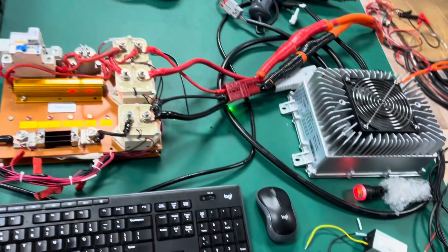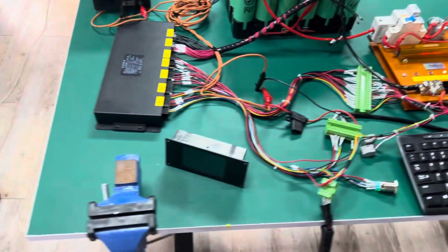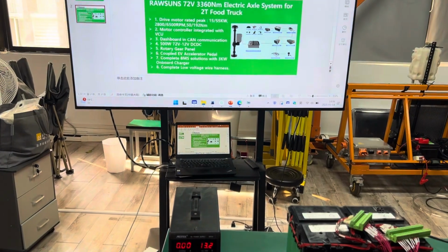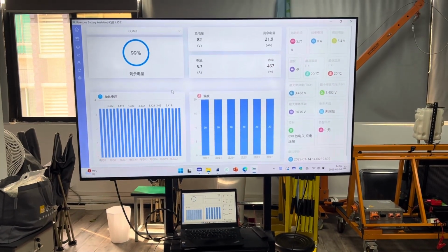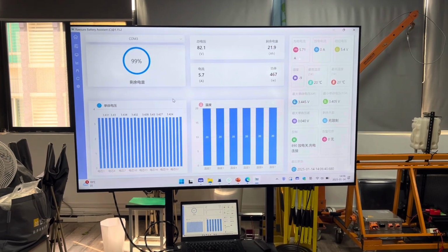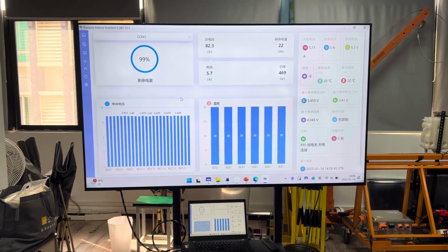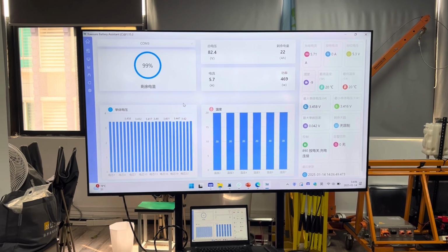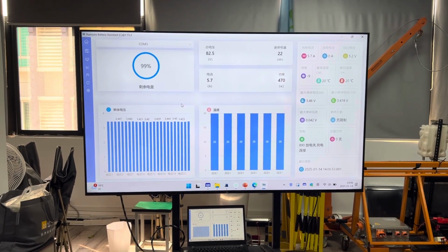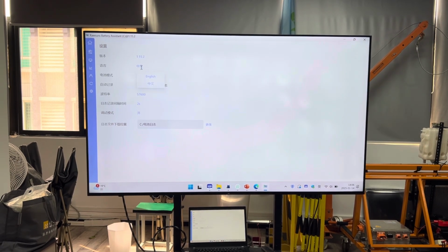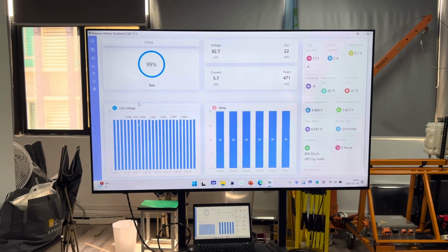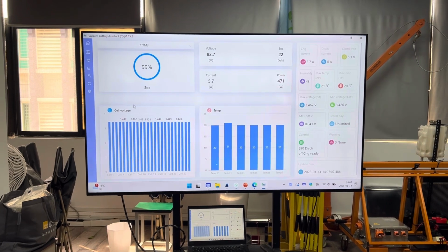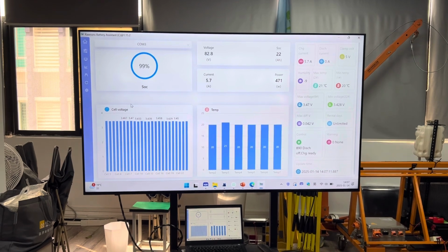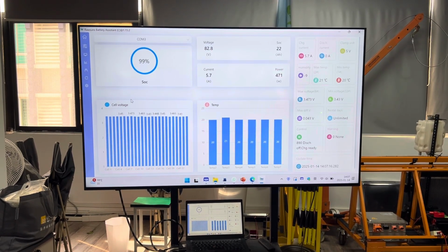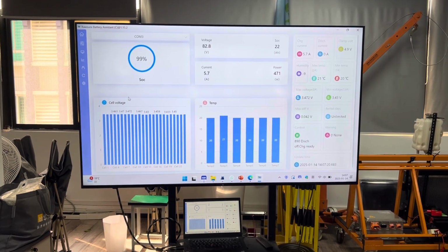now the 3 kilowatt charger is connected to the BMS system. We can have a look at our software. We can see on the screen now the charging current is about 5.7 amps at a voltage of 82.3 volt, and let me change to English. All the cell voltages we can read on the screen, and the temperature of the battery pack is also shown on the software, and the maximum voltage and the minimum voltage of the battery pack are also shown on the software.